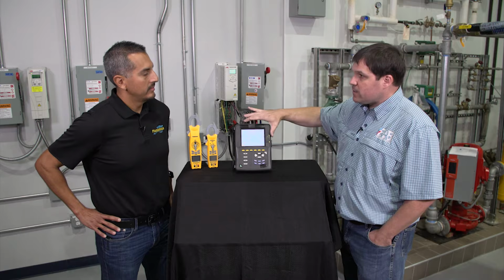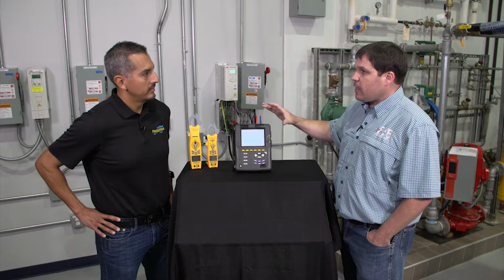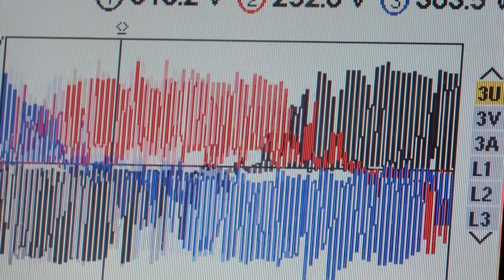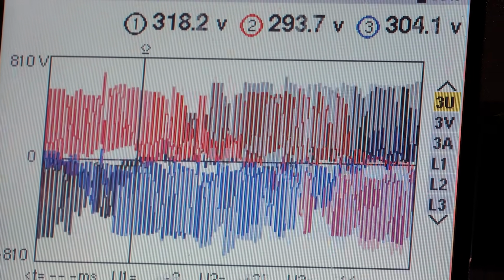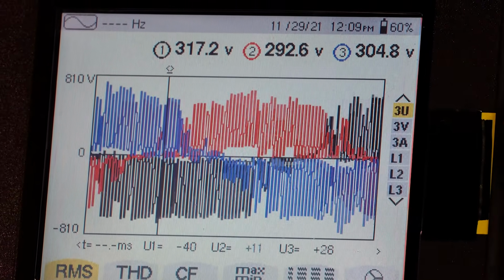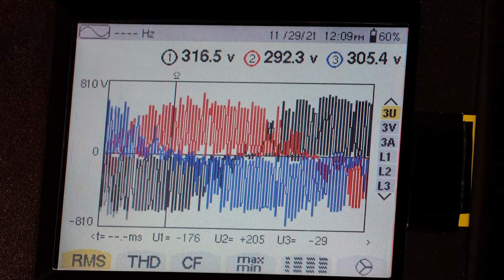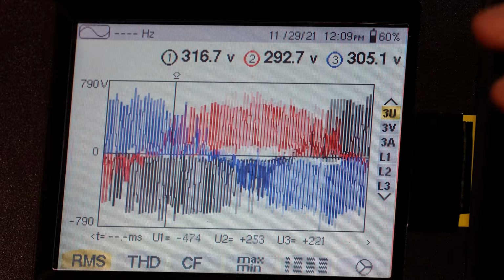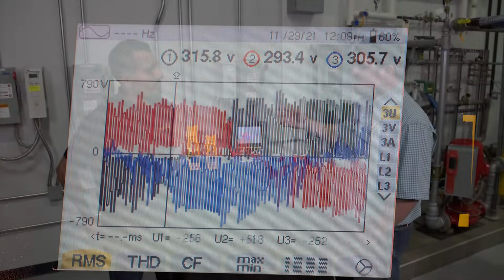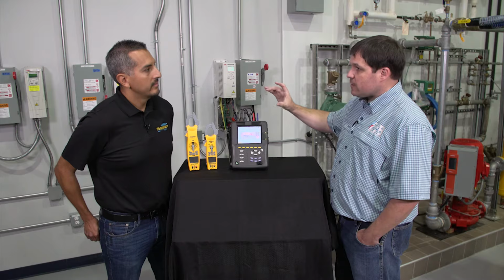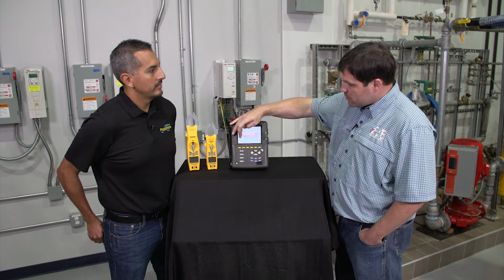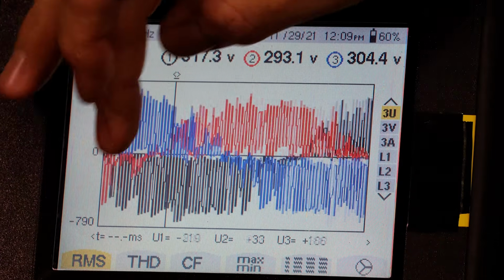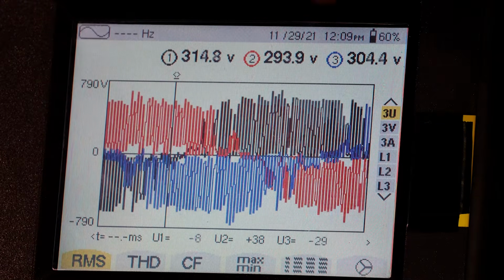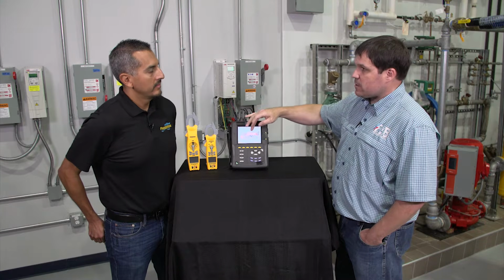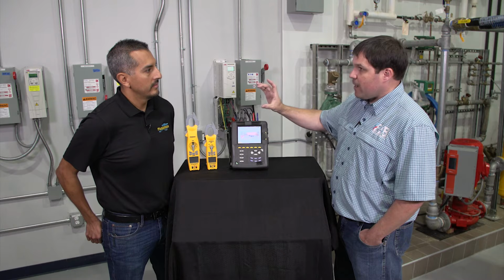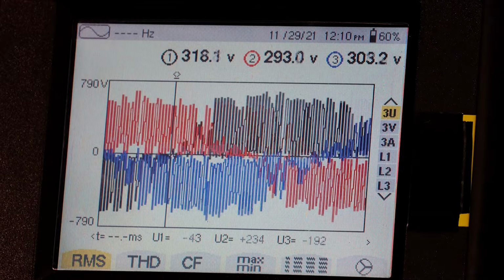Next we'll need to change this and see the signal coming out of the VFD and show why it's different. So Tony, what we have here is a signal actually output from the VFD, and you can see it's quite a bit more noisy than that perfect sinusoidal wave we saw entering. The reason is this VFD converts the AC signal from the utility company into a DC signal, then manipulates that signal to make it look like an AC sine wave. It pulses to control torque and speed of the motor. So what the motor actually sees is an average of this signal. But if we're using a meter that doesn't have filtering technology, it will pick up these pulses and measure a much larger amplitude than what the motor is actually seeing in that average, giving an inaccurate reading.